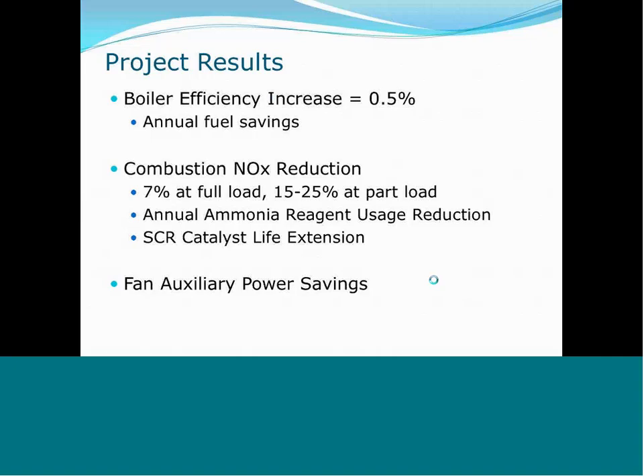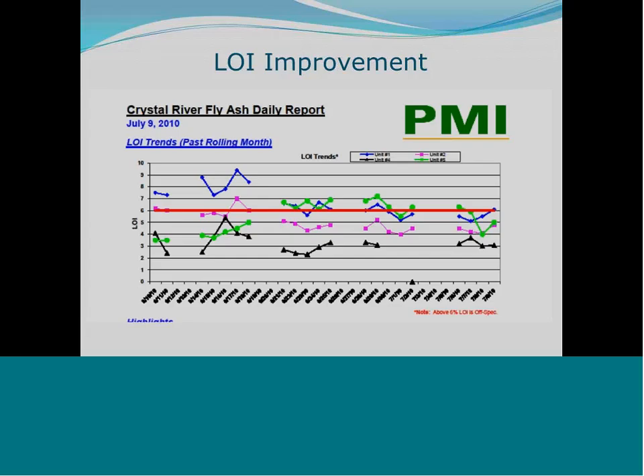And these are their project results: 0.5% improvement in efficiency, which has given them a couple million dollars a year in fuel savings, as well as a NOx reduction. Now, this particular plant has SCRs, so NOx was not a driver, but they did get NOx reduction at the inlet to the SCR, which is going to help with ammonia consumption. They had a decrease in unburned carbon, which makes the red line being the sellable line. Unit 4 is the black curve. They can always remain sellable with their ash.